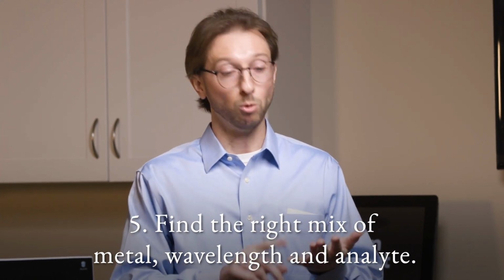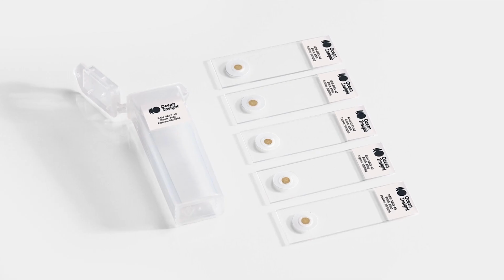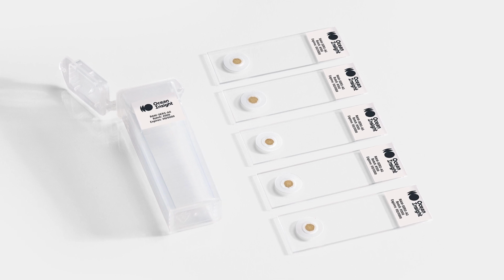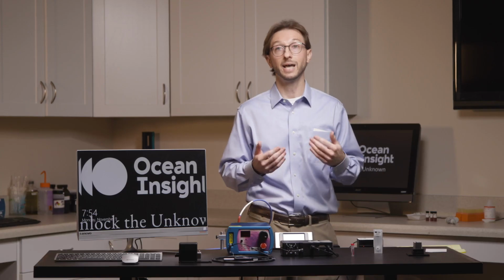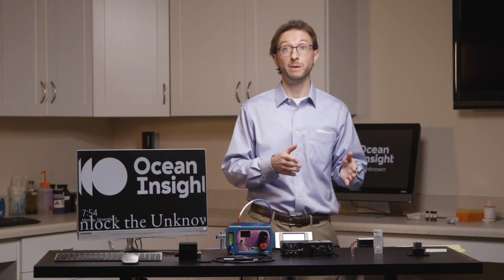Well, we offer both gold and silver SERS substrates. You want to pick a metal that's in tune with the laser wavelength. Additionally, there's certain analytes that have a higher affinity for a certain metal. So that's one of the key things to make sure you're really getting the right combo of the metal type, the analyte, and that wavelength so that they're in tune with each other and you're getting the most out of your Raman signals.